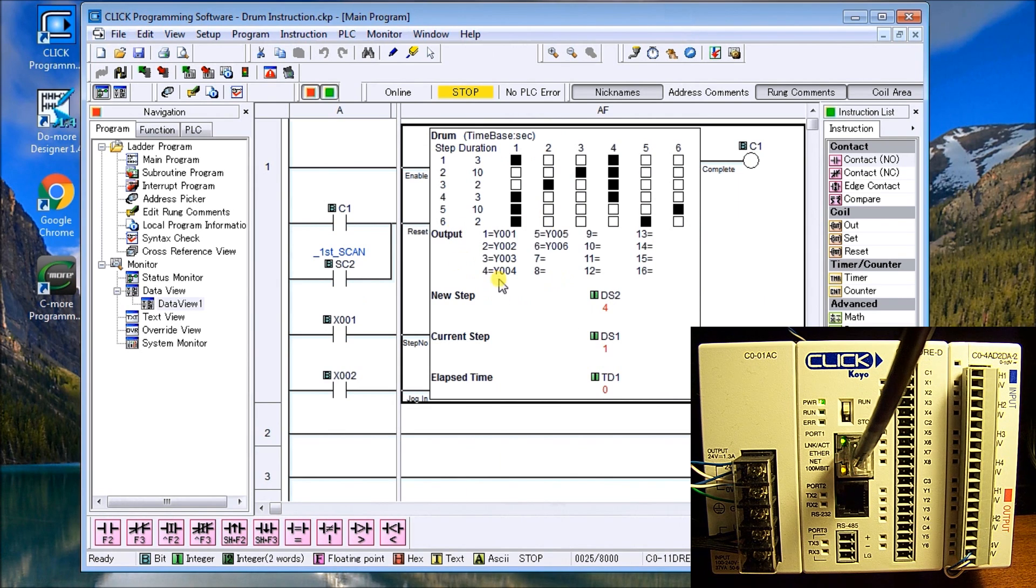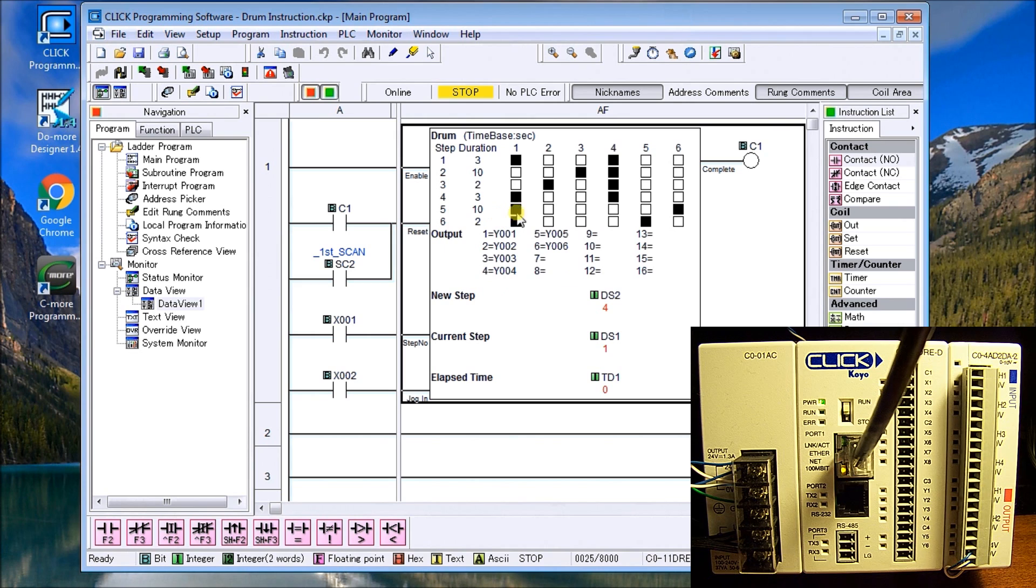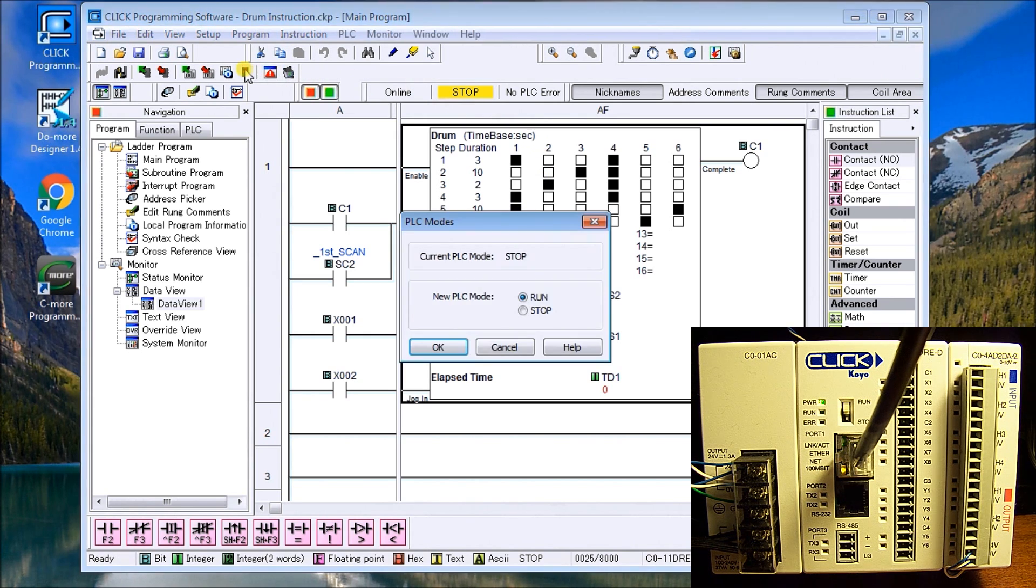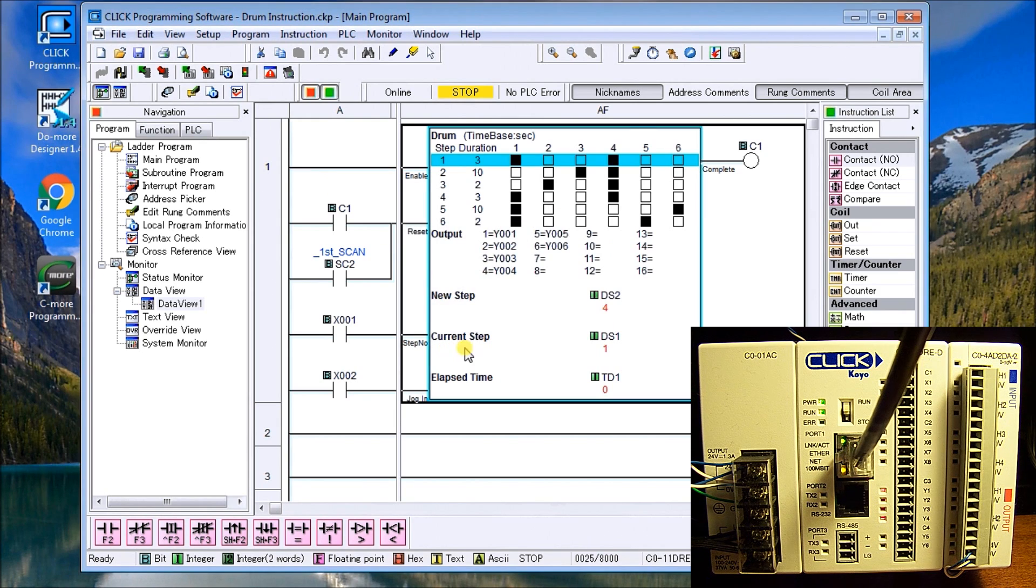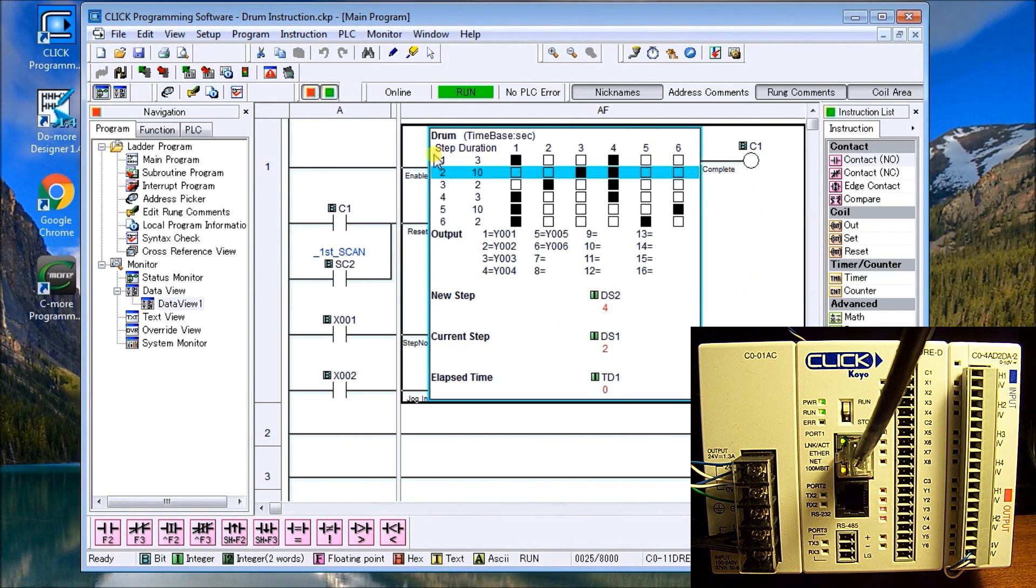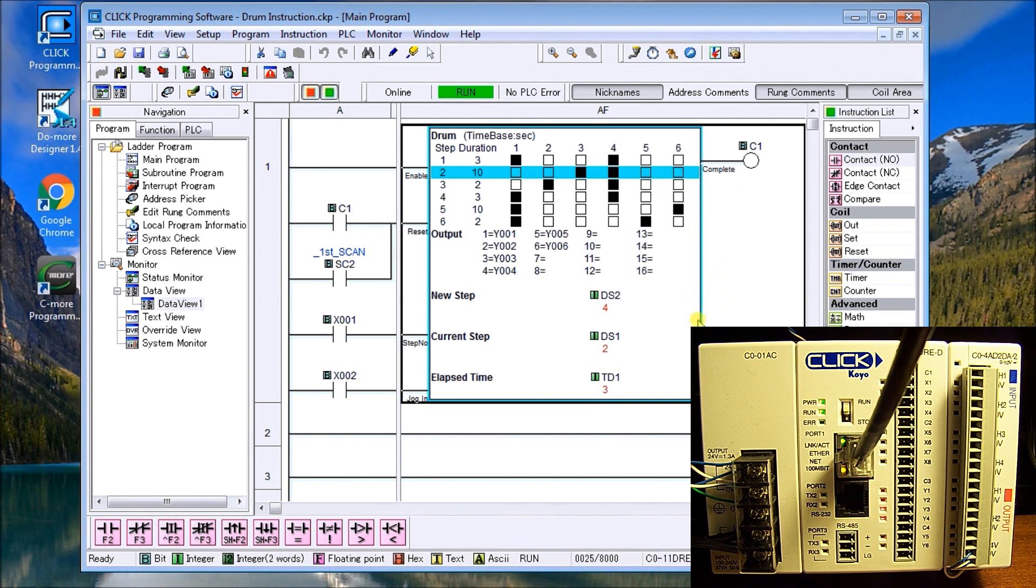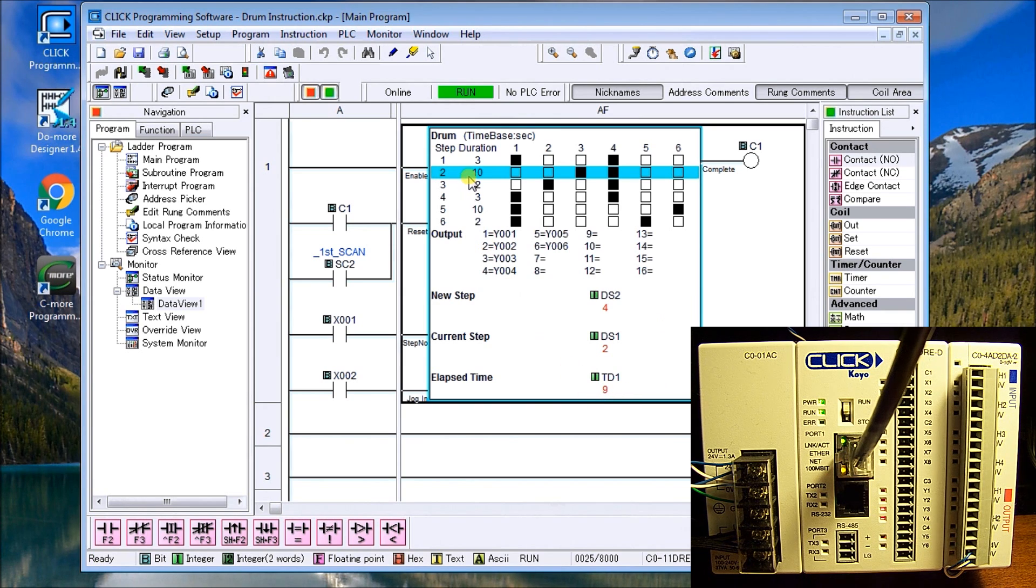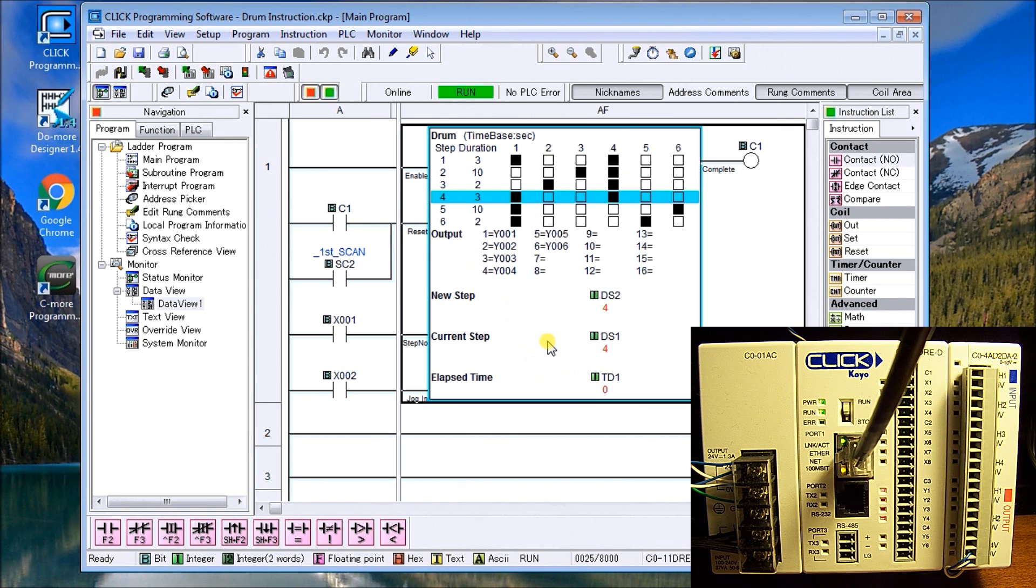Currently right now I am hooked up to my PLC and what we'll do is we will go into run mode and see how it looks. And as you can see here's my run mode, it highlights what step I'm on. On a detailed instruction I can see here, here's my time value, I can compare that to my time duration here, 10, and then it will move to the next step. My current step right here we see we're on number four and it's cycling through our instruction.